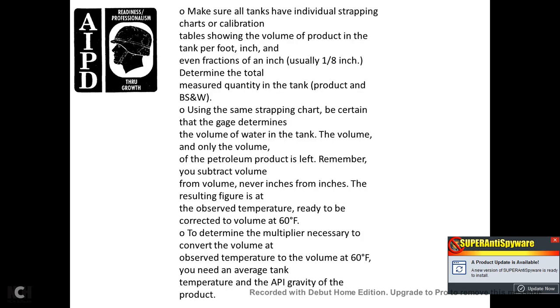Make sure all tanks have individual strapping charts and calibration tables showing the volume of product in the tank per foot and inch — even fractions of an inch, usually one-eighth — to determine the total measured quantity and the bottom sediment and water. Using the same strapping chart, determine the volume of water in the tank and the volume of product only. Subtract the volumes — remember, always subtract volumes, never inches. The resulting figure is the observed volume that needs to be corrected to 60 degrees Fahrenheit.